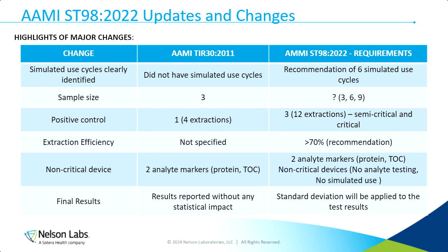In ST98, simulated use cycles are identified, whereas in TIR30 they were not mentioned. There are some changes with sample size. There are changes with the positive controls and extraction efficiencies. One of the biggest is going to be non-critical devices and how we treat and validate those. It's nice for manufacturers because the requirements for validation of non-critical devices are a lot less strict. And then the last thing we will discuss is the final results and the statistical impact of those.